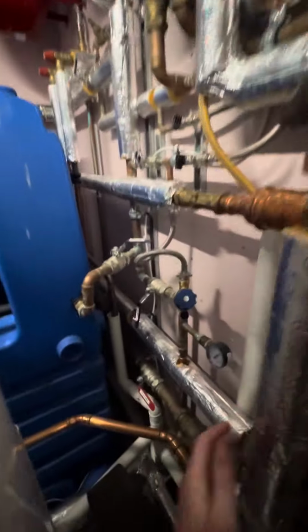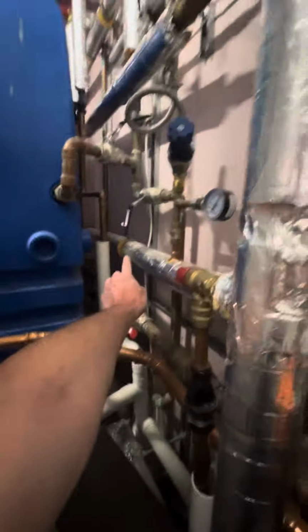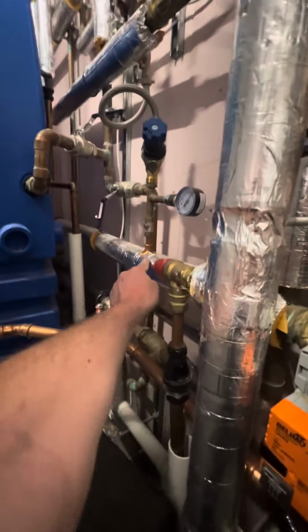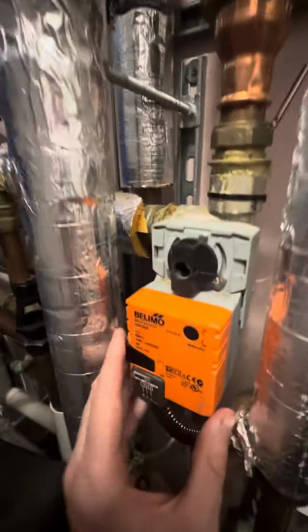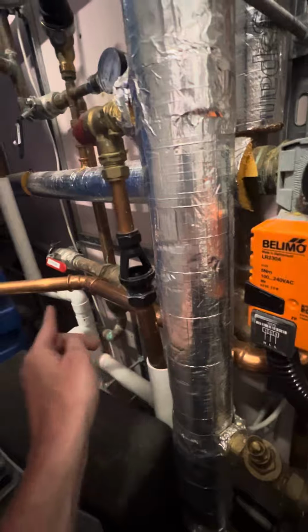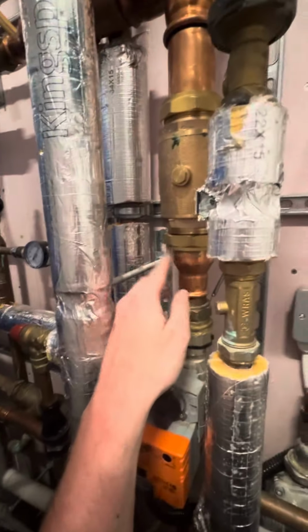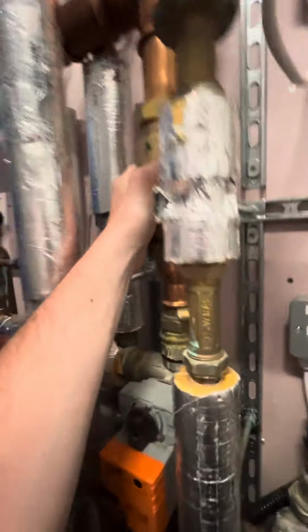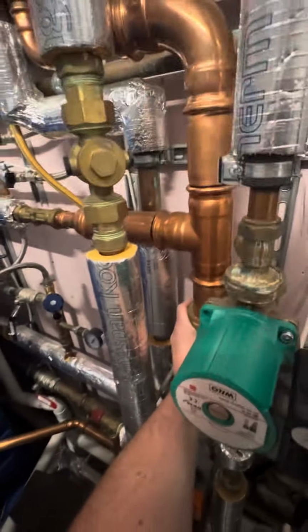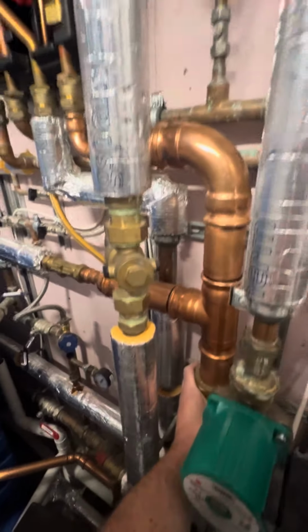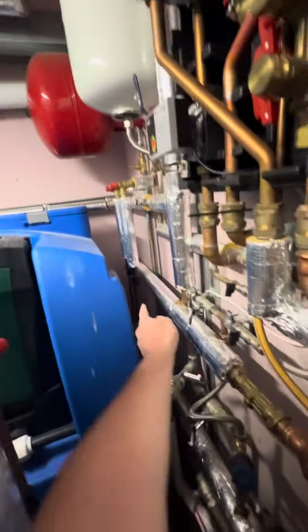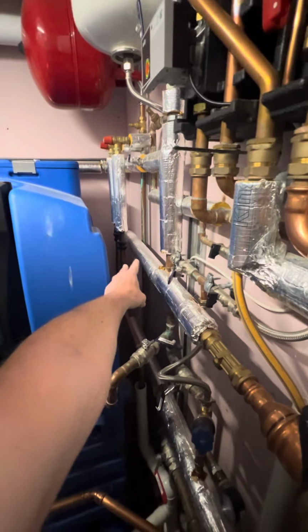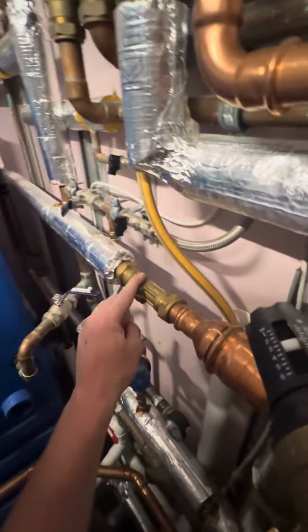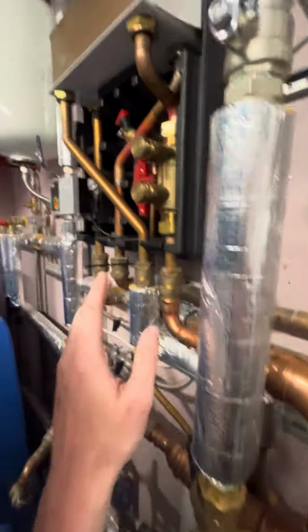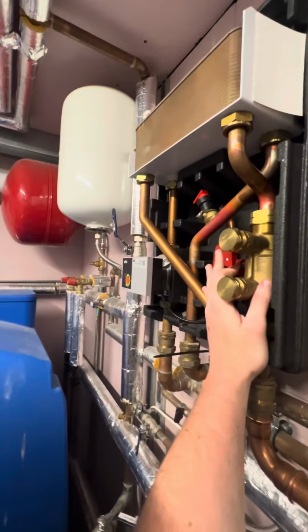So how this works, we've got the flow from the heat pump that can do heating and hot water, comes in through here into this nice Belimo diverter valve, down here to hot water, or up here to central heating through this non-return valve, if it's ever required, if 2 heat pumps are required and 1 heat pump can't provide enough heat. The other heat pump, which is the primary heat pump for heating and only does heating, flow comes in here through this non-return valve and up here into this Vaillant plate heat exchanger system here.